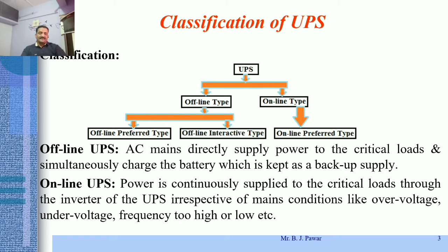So first of all, we will see in detail the offline UPS. There are two types of offline UPS, that is, preferred type and interactive type. The first one we will see is the preferred type. The block diagram is shown here. There is AC mains of 230 volt RMS, 50 Hertz. It is connected to the first static switch S1, which is written as normally on. The AC mains is connected to the load through static switch S1 continuously. That's why it is written as normally in on condition.